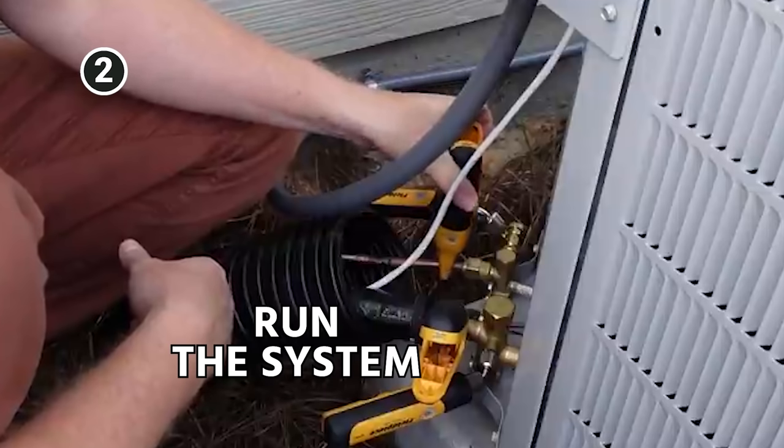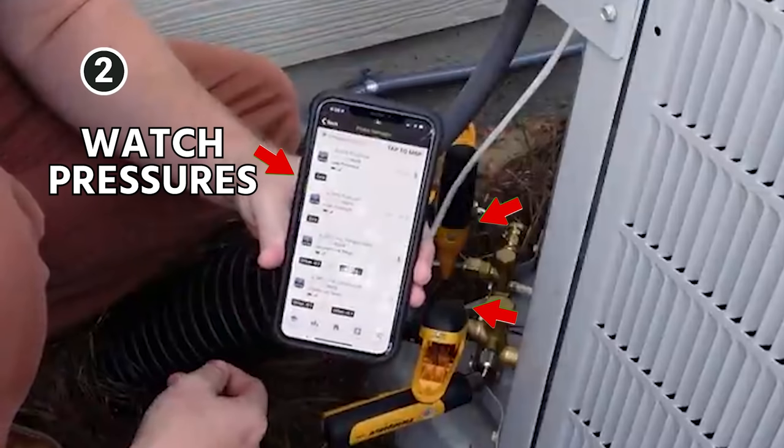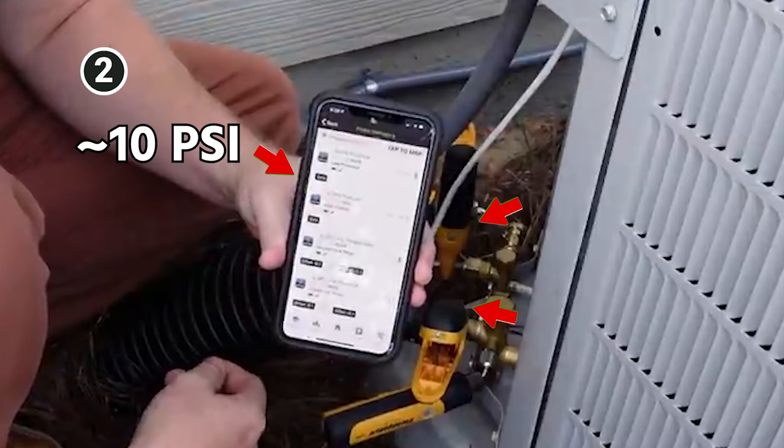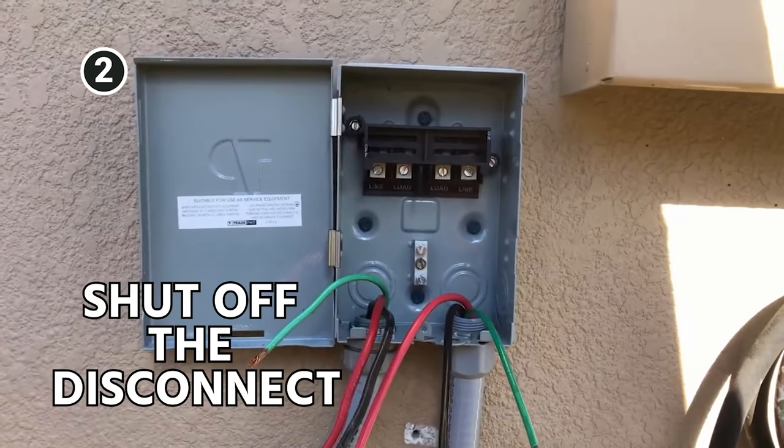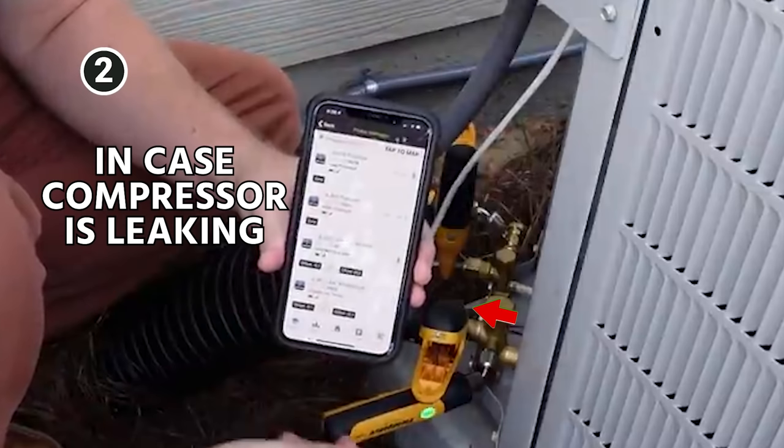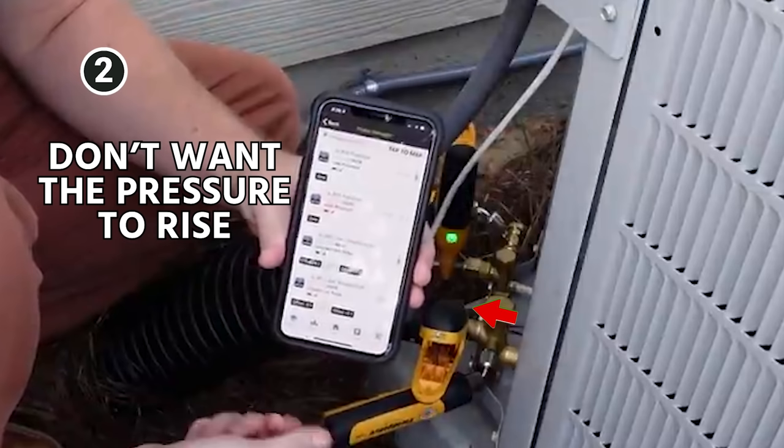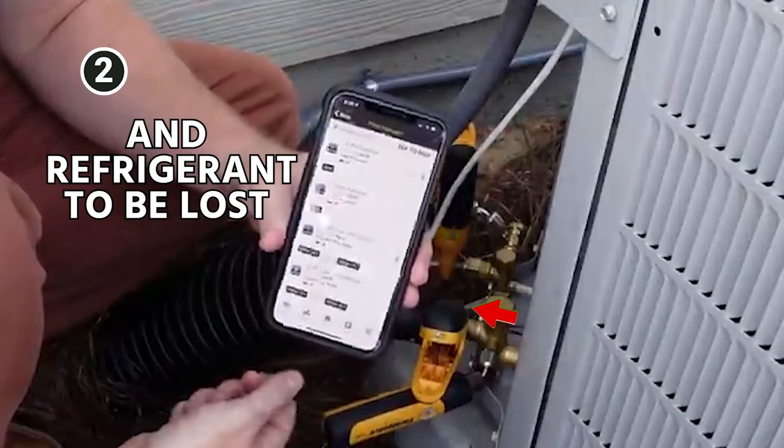You're going to run the system and watch your pressures on both your suction and your liquid side. They're going to drop generally pretty quickly, often about 10 PSI. That's when you want to go ahead and shut off the disconnect and then also shut down the suction valve at the same time, just in case your compressor is leaking a little bit through the valves. You don't want that pressure to rise and that refrigerant to be lost.